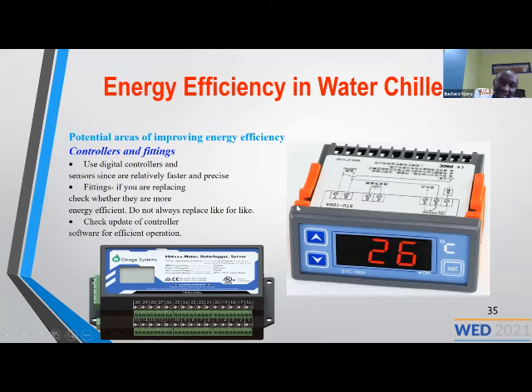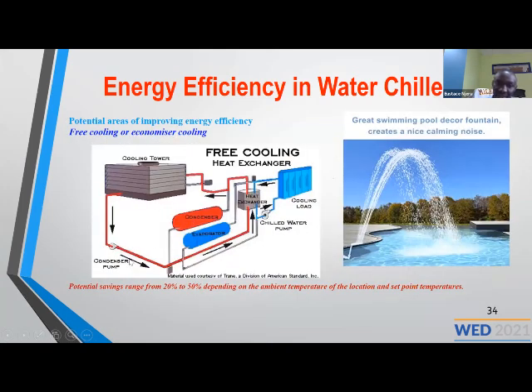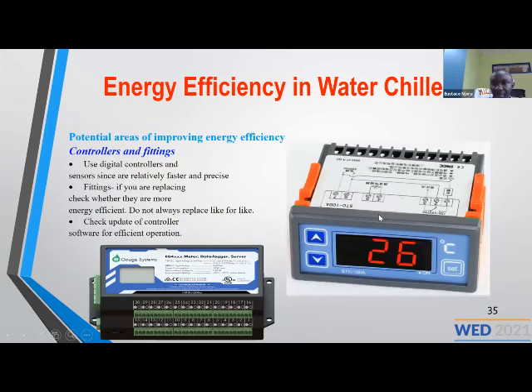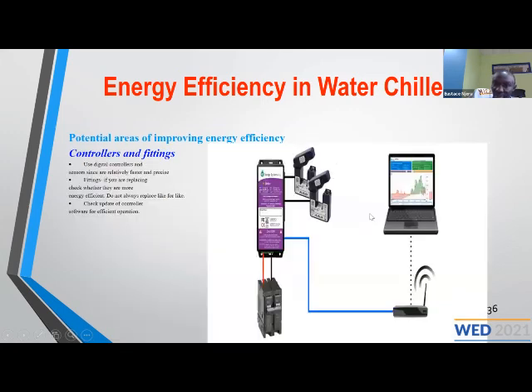The other one is using an integrated automatic control system, where you can monitor temperatures in the condenser, evaporator, the water, and so on. You use it to know which parts to switch off: when to switch off the cooling tower fans, the cooling tower water, the fans, and so on. Integrate all of them, and in such a system, you can save a lot of energy.